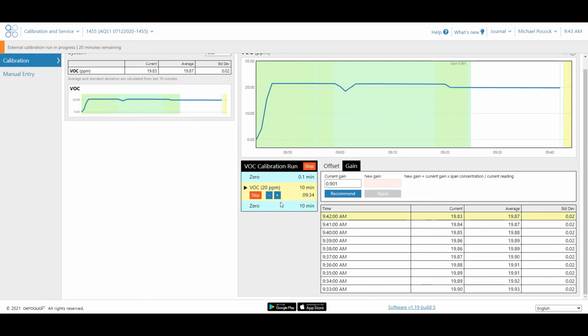So if we have a look here at the last 10 numbers, I've been feeding isobutylene gas to the monitor for at least the last 10 minutes. And you can see these numbers are quite stable. So we've got 19.83. This is our last reading. Okay, so we have a very low standard deviation, and we're actually within our tolerance here. So the tolerance for a span calibration is 5% of the span concentration. So 5% of 20 ppm in this case.